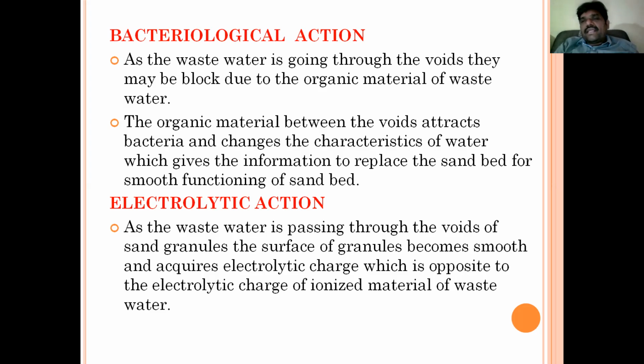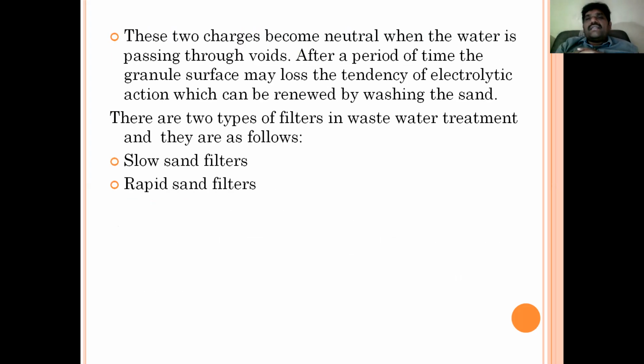But this electrolytic action will become neutral. After a period of time, the granule surface may lose the tendency of electrolytic action, which can be renewed by washing the sand. After a period of time, the surface of the voids becomes smooth and loses its electrolytic action, which gives the information of the need of changing the sand bed.